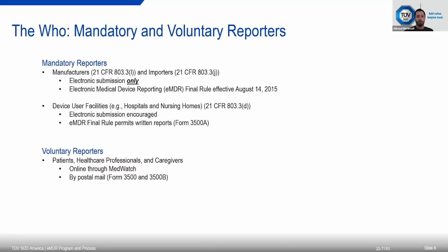This is also important to mention that an MDR report does not constitute an admission that the device reporting entity or the entity's employee caused or contributed to the reportable event. This is an important disclaimer because without it, FDA probably wouldn't receive enough MDR reports in order to conduct post-market trending and carry out its mission of protecting the US public health.